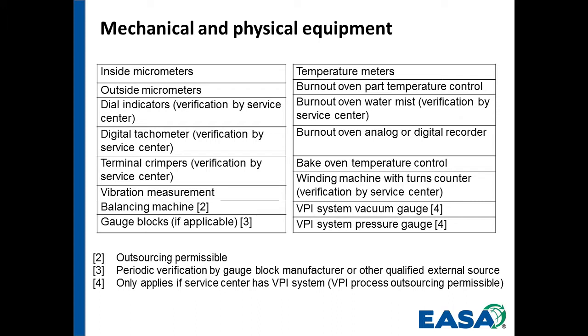Mechanical and physical equipment: the left-hand column is the mechanical, the right-hand side is the physical equipment. Inside and outside micrometers: many service centers use the outside micrometers with calibration on them to measure the values that are measured with the inside micrometers. In other words, the inside micrometer is simply used as a gauge. Other items, dial indicators, digital tachometer, some of these have verification processes because they don't lend themselves to calibration, like a terminal crimper would not be calibratable, let's call it.